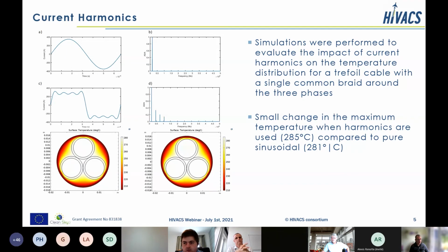I think you've got to be careful, of course, making the conclusion that harmonics don't give you significant temperature rise. That may vary as a function of conductor cross-section. So as conductors get larger, things like skin effect, proximity effect, and the effect of harmonics will only increase.